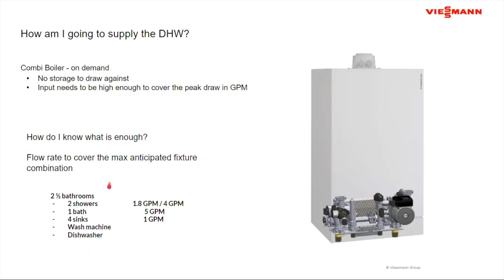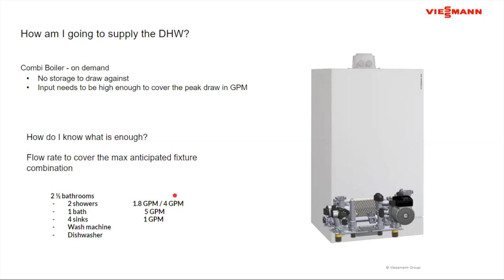So if I come down to these fixtures, there are two showers, one bath, four sinks, a washing machine, and a dishwasher. These two showers, we'll call it 1.8 gallons per minute each, or if I'm running both of them, 5 gallons per minute for the bathtub, 4 gallons per minute for the sink. So the question becomes, what do you think is going to be the maximum combination you see? The bigger the combination, the bigger the combi boiler has to be. In most cases, somebody would say, let's size it based on having the two showers running. Let's go with 4 gallons per minute as our initial look at domestic hot water.